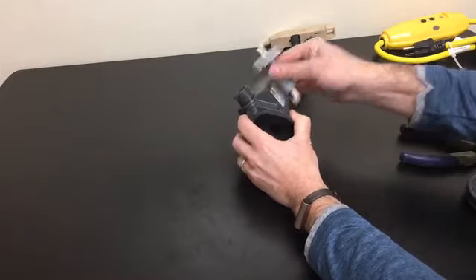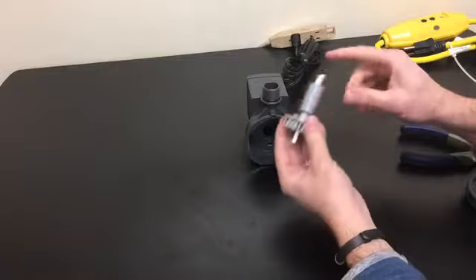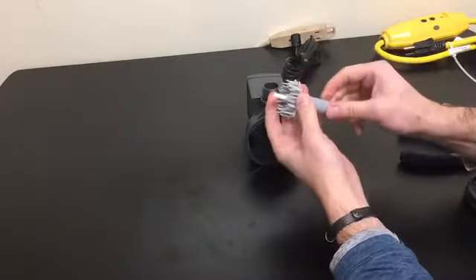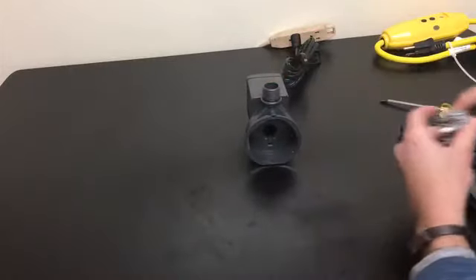So you can feel the vibration on any pump, and you know the motor block's good. So if I'm having any kind of issue at all, it's in cleaning these rotors, it's in the bearing, front or rear. It's something to do with the rotor or the bearings or the shaft. It has nothing to do with the motor block.